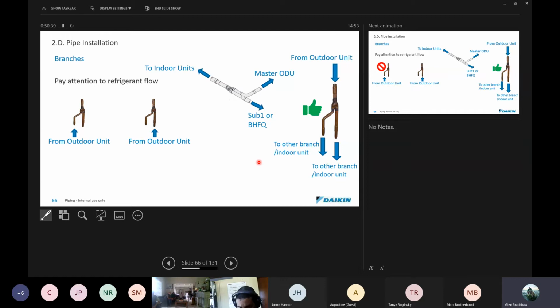All right, branch kits, just to get onto the rules of those. First of all, and believe me, we've seen this, where guys, instead of using the inlet of the refrigerant into the Y joint from this direction over here, they come in from one of the two Y joints. You cannot do this. The Y joint is designed to spread the refrigerant flow evenly. It's as though you were driving down a road and you came to a Y section. It's a lot easier if you're approaching the two from the straight side. You can decide whether you want to go left or right, where if you're entering from over here, it's very difficult to come back and make a U-turn down here. So think about the refrigerant in the system as well.